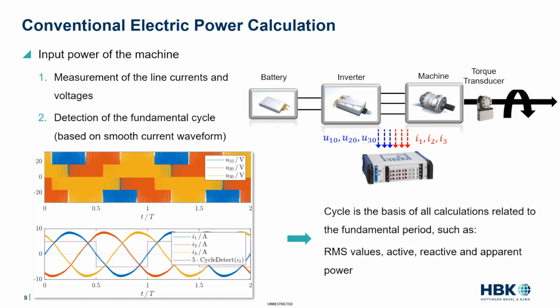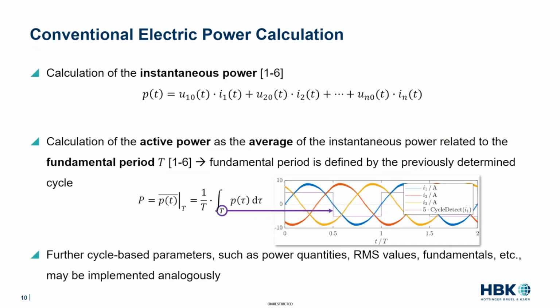Now that we have the measured voltages and currents correctly detected over this cycle, let's look at how power is calculated. As is well known, the instantaneous power in each phase equals the product of the corresponding measured voltage and current. This is done for each phase, and to get the total instantaneous power, you sum over all phases. Then, in a second step, we average this instantaneous power over the fundamental period, T, which is the cycle we detected. This averaging is done to calculate active power.